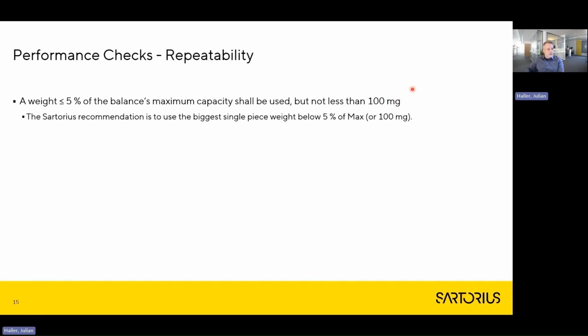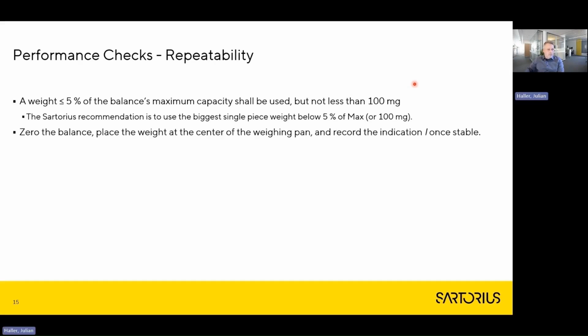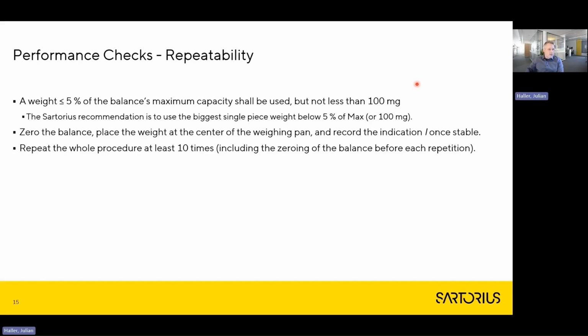For the repeatability performance check, use a weight of smaller than or equal to 5% of the balance's maximum capacity, but in any case, not less than 100 milligram. Our recommendation is to use the biggest single piece weight below 5% of max, or 100 milligram. For the test itself, zero the balance, place the weight at the center of the weighing pan, and record the indication once it is stable. Repeat the whole procedure at least 10 times, including the zeroing of the balance before each repetition.